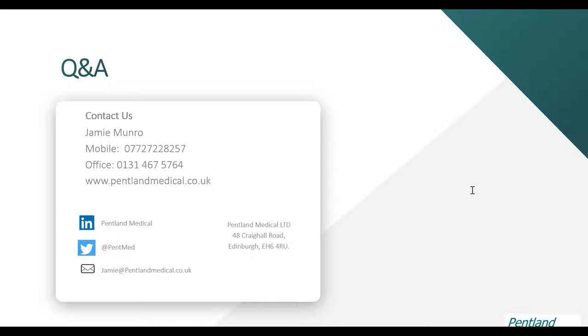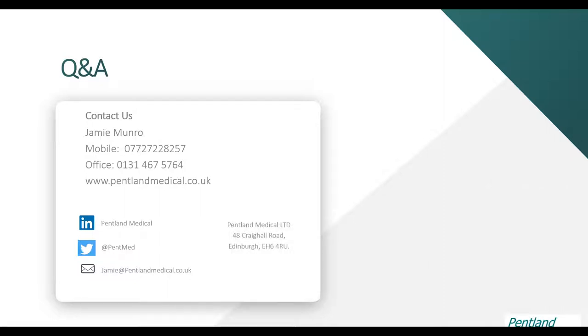The reason you have to readjust the sets isn't because of Monidrop itself. It's more to do with the administration set, because the tubing walls are different thicknesses and can slide, or the roller clamp quality can affect it. Sometimes you need to readjust the flow a little later, but after one readjustment it tends to stay okay.